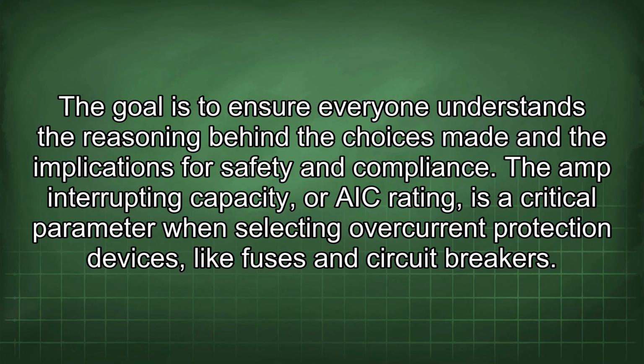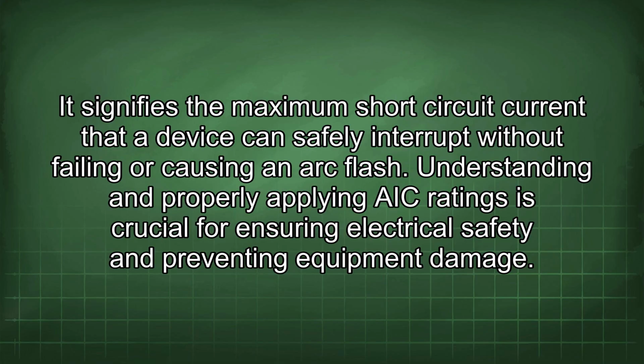The amp interrupting capacity, or AIC rating, is a critical parameter when selecting overcurrent protection devices, like fuses and circuit breakers. It signifies the maximum short-circuit current that a device can safely interrupt without failing or causing an arc flash. Understanding and properly applying AIC ratings is crucial for ensuring electrical safety and preventing equipment damage.